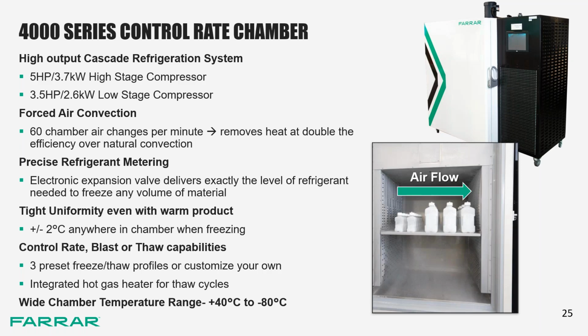And finally, the electronic expansion valve meters the refrigerant, so when you do not need all that cooling capacity, such as when you're ramping down and holding at a specific temperature, the unit can quickly reduce the amount of refrigerant to control the freezing rate and then expand it again when it's needed. ULTs typically use a fixed cap tube, which is dialed in to be most efficient at -70 or -80 degrees and the amount of refrigerant needed to maintain that steady state and account for an occasional door opening.